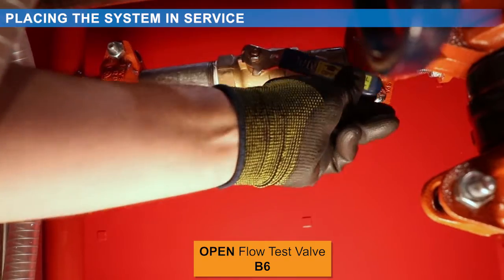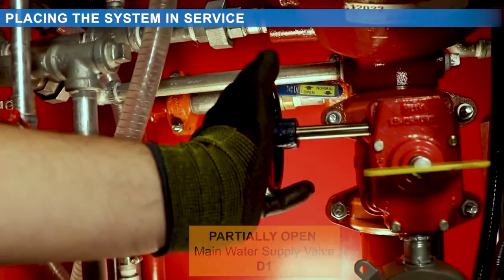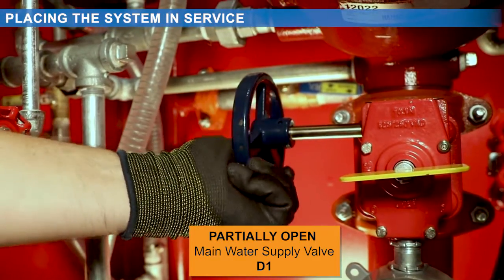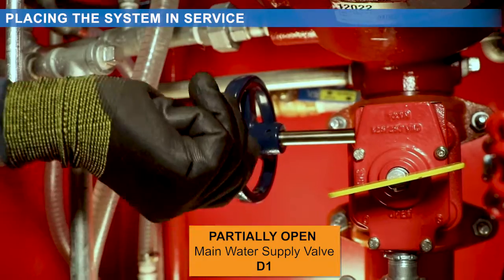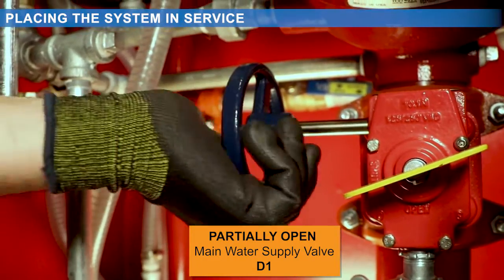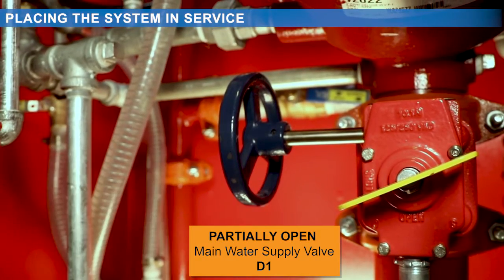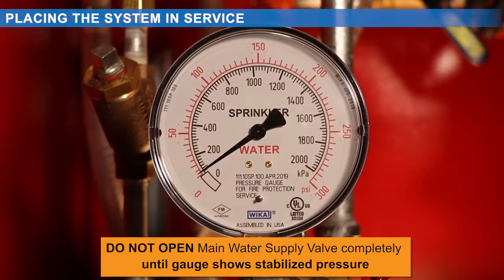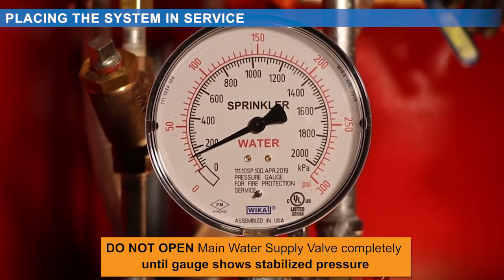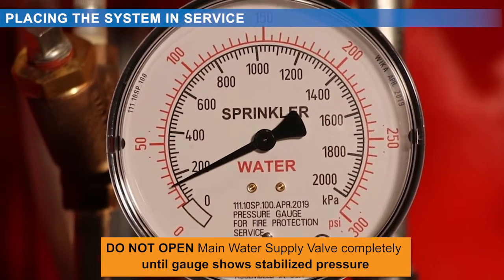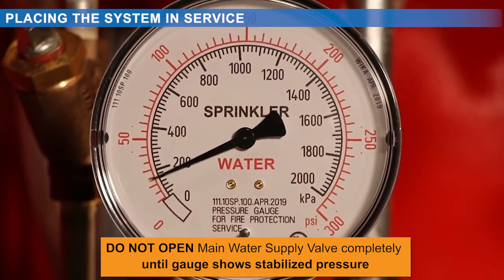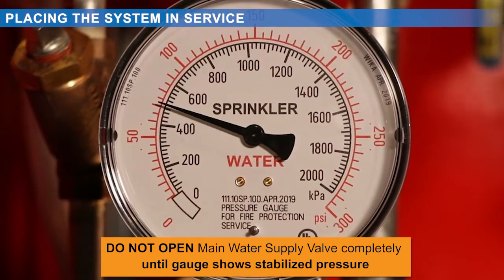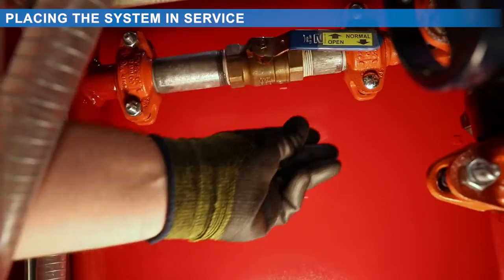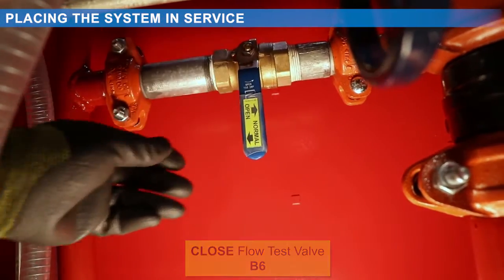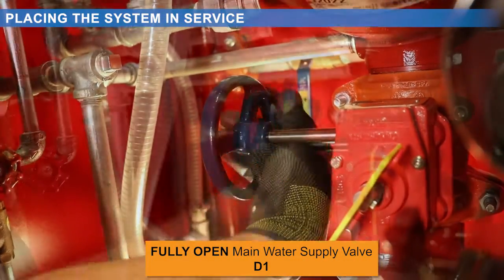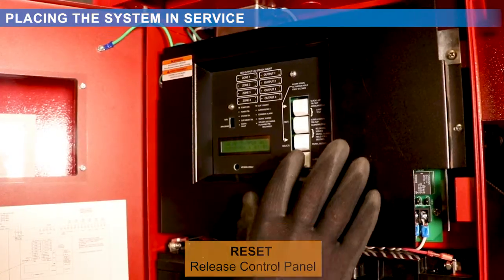Open flow test valve. Partially open main water supply valve until a water flow is heard. Do not open main water supply valve completely until gauge shows stabilized pressure. When full flow develops from the flow test valve, close the flow test valve. Fully open the main water supply valve. Reset the release control panel.